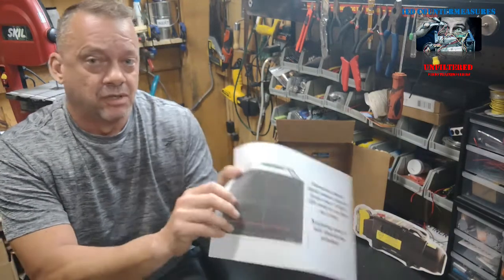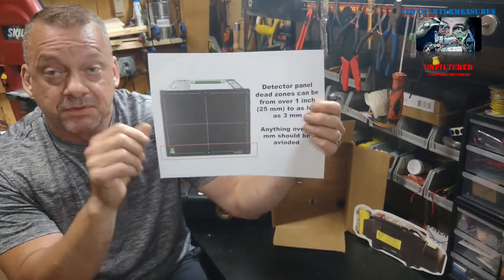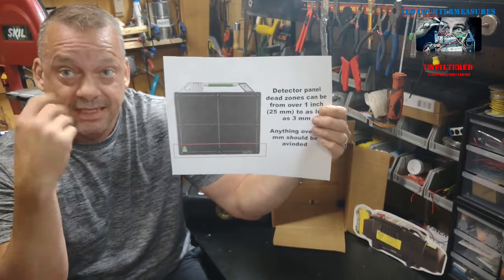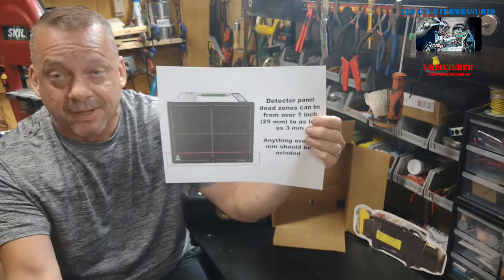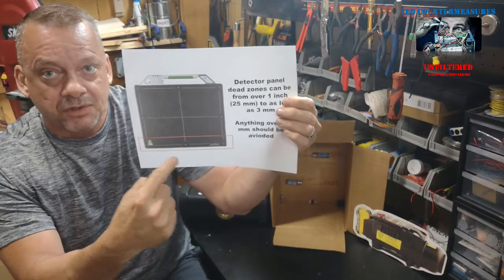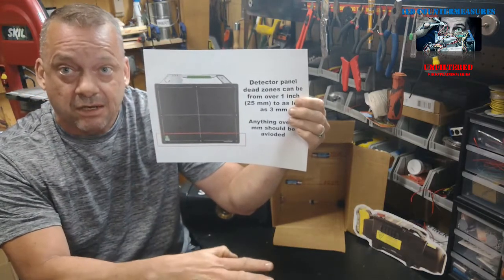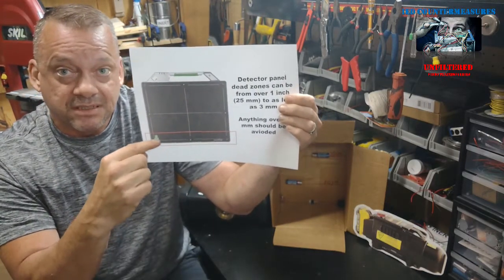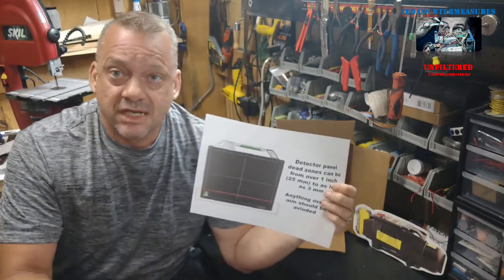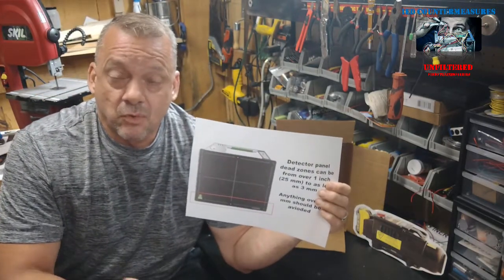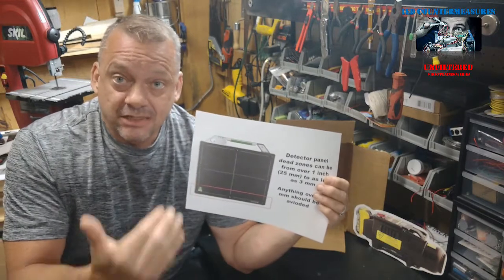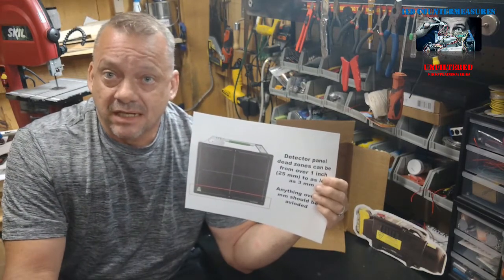The one thing most people know and think is the only real reference to lower edge cutoff, or the dead zone at the lower edge of the panel, is with your digital radiography panels, especially the amorphous silicon ones. Again, I've told you before, these are medical panels. They can have a lower zone, and if you're scanning on the ground, this is where it becomes very important, because that lower dead zone is not going to get imaged in your x-ray image. So whatever's in the package that's below that is potentially not going to get imaged.